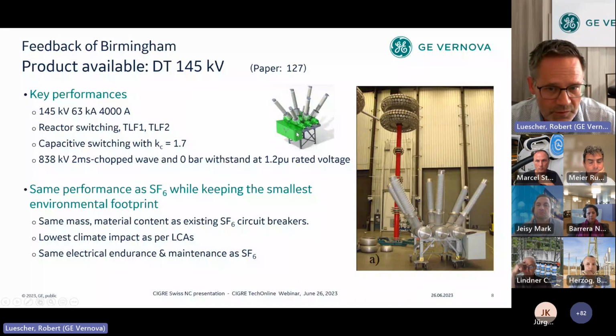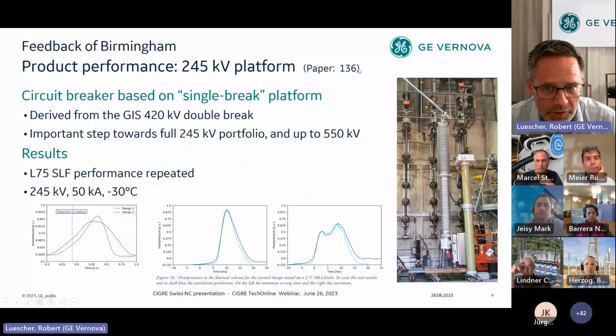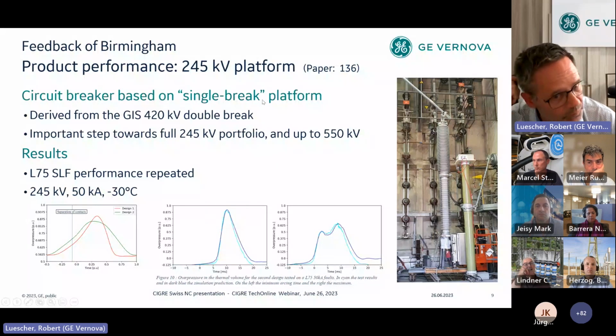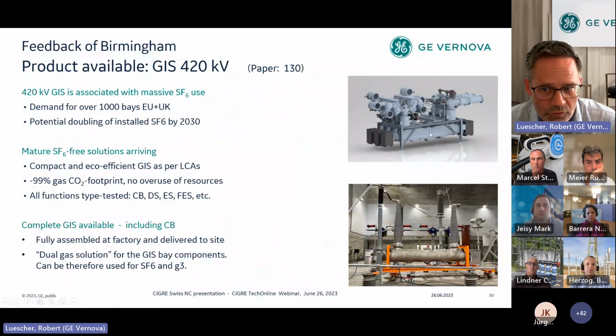Same story, just an example - paper 136. Here is the demonstration of a single break platform, meaning one single interrupter for a 245 kV AIS breaker. This is more or less a derivative of our GIS 420 kilovolt breaker, which has 2 interrupting chambers in series. If you take only half of it, you get the AIS circuit breaker shown in the previous paper.